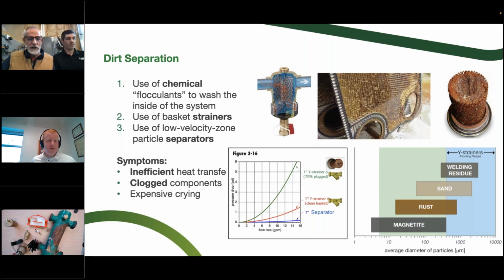So when we talk about pumps, we say you never want to put a flow restricting device on the suction side of a pump, but that's kind of where you'd want your Y strainer. But if a Y strainer ended up in that condition there, that pump's not going to be very happy. You're going to be cavitating that pump, and you're going to have pump problems in addition to flow problems in the system. You can see at 70% plugged up there what the pressure drop is. If you had a pump that's only developing 10 PSI or 10 feet of head, it's barely going to go through that strainer when it's plugged up that much.